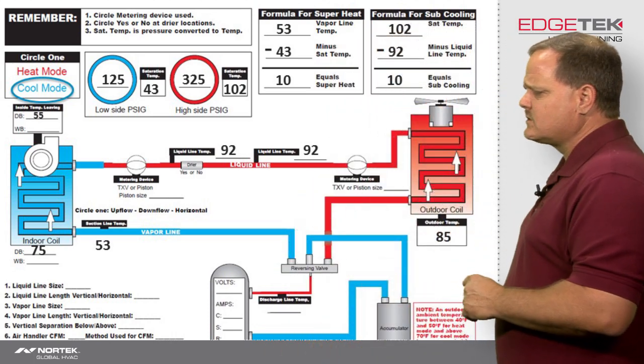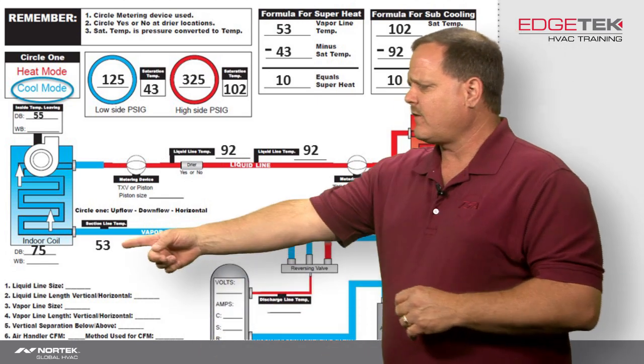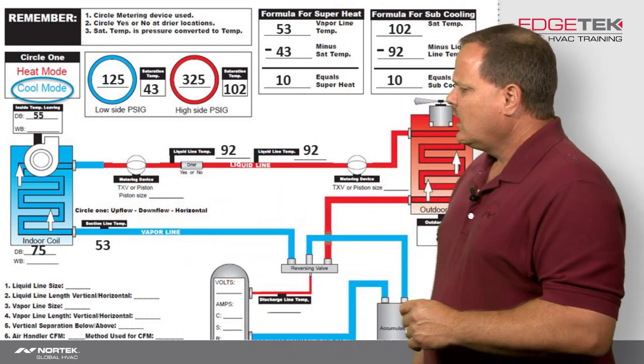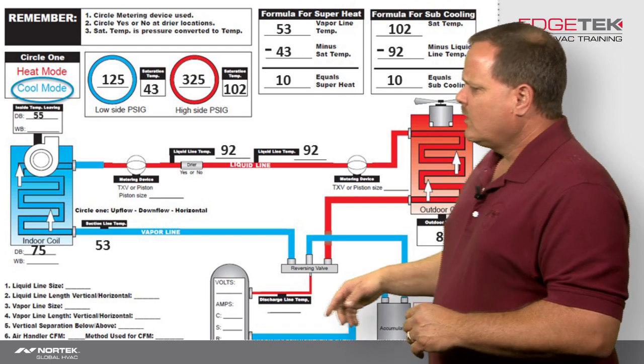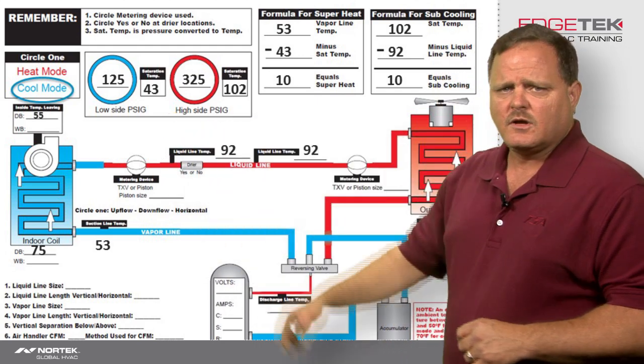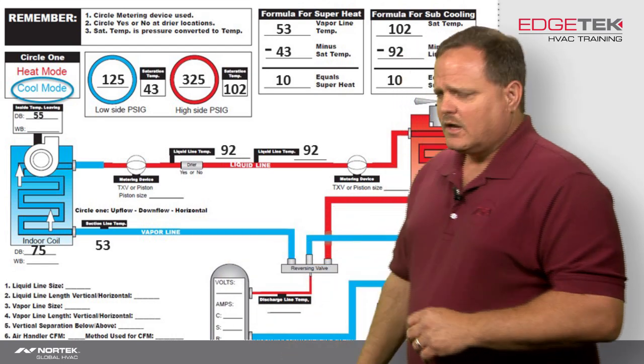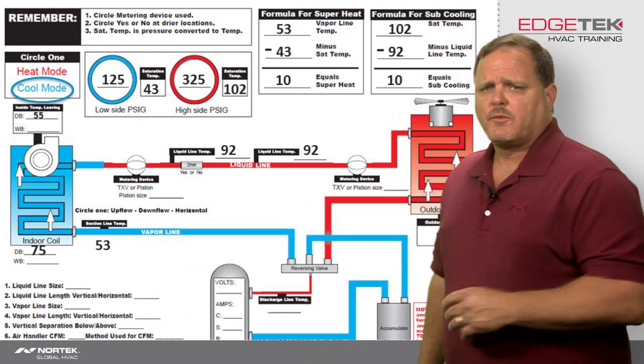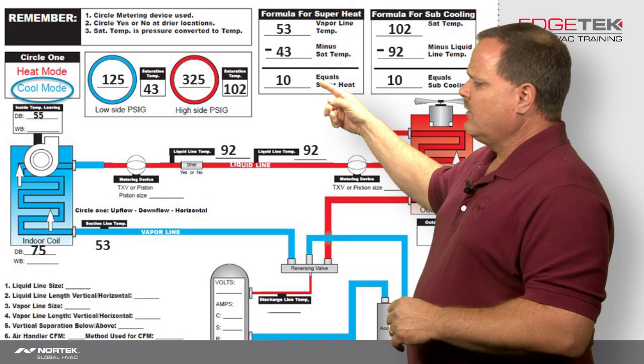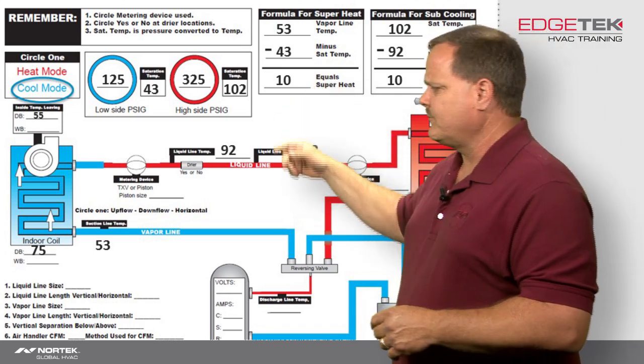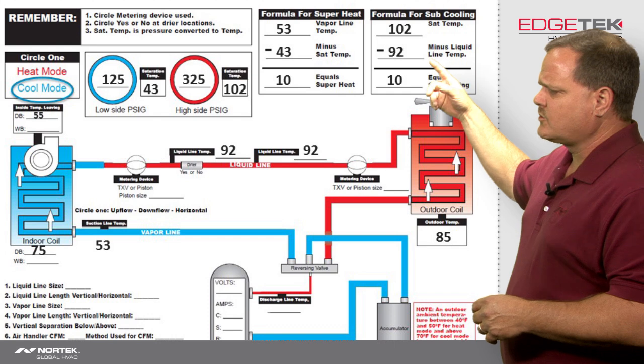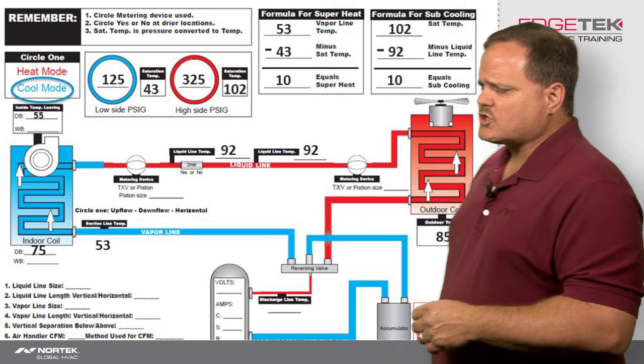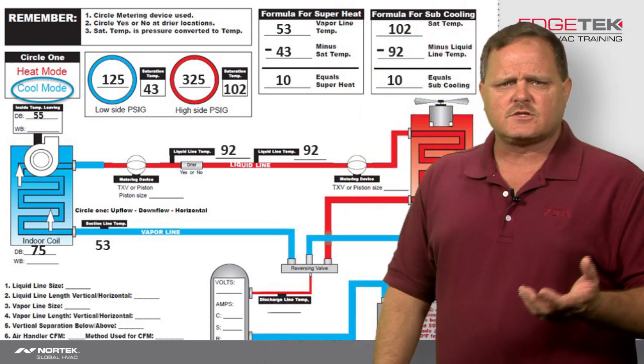This is a normal operating system. We're in cool mode. We've got a 75 degree indoor temperature and a 55 degree leaving temperature — that's a 20 degree temperature drop across the coil. Outside we've got 85 degree entering condensing temperature, 125 pound suction pressure, 325 pound head pressure, 92 degree liquid line temperature, and a 53 degree suction line temperature. When we throw it into the formulas: 53 minus 43 gives me 10 degrees of superheat. On the subcooling side, we've got 102 degree condensing temperature and a 92 degree liquid line temperature giving me 10 degrees of subcooling.